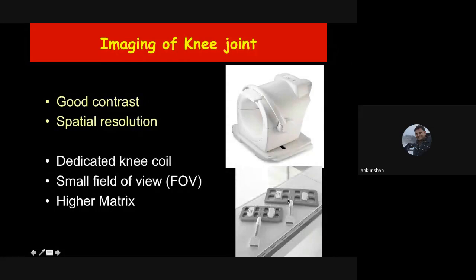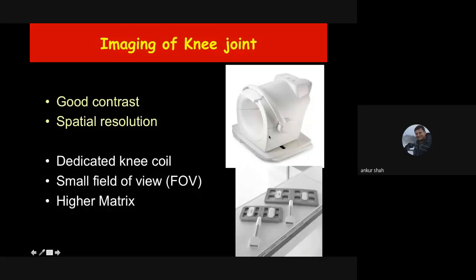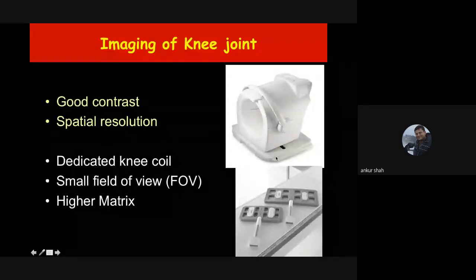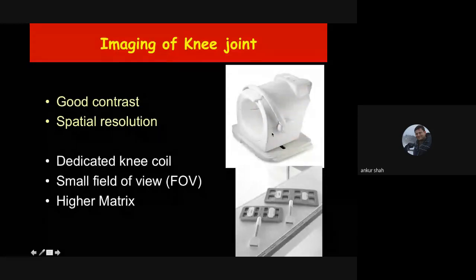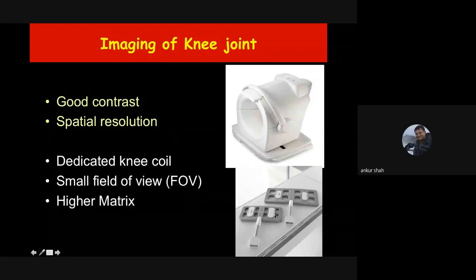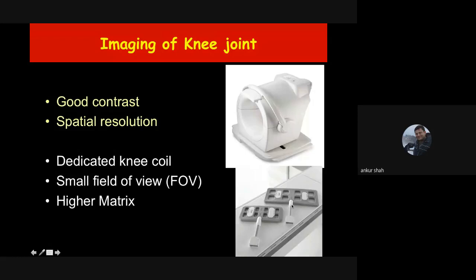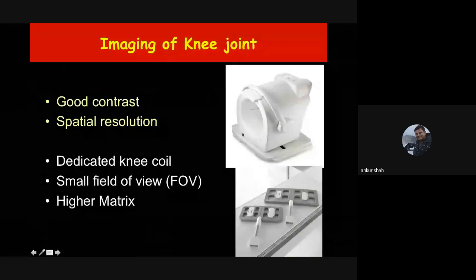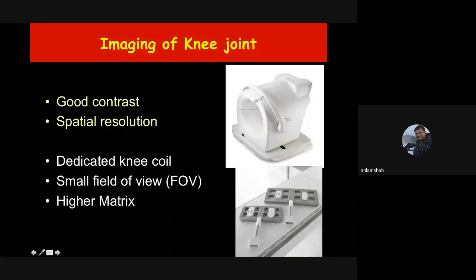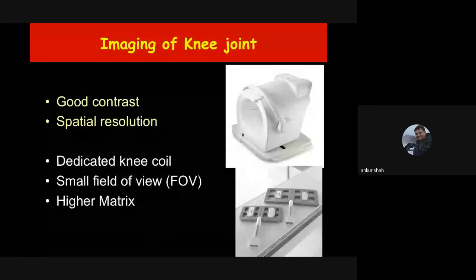Some people, due to extra cost, don't purchase the dedicated knee coil and try to do MRI with flexible coils. You do get MR images but the image quality is usually not as good as with a dedicated knee joint coil. This applies similarly to the shoulder and wrist — there are different coils for almost all major joints.